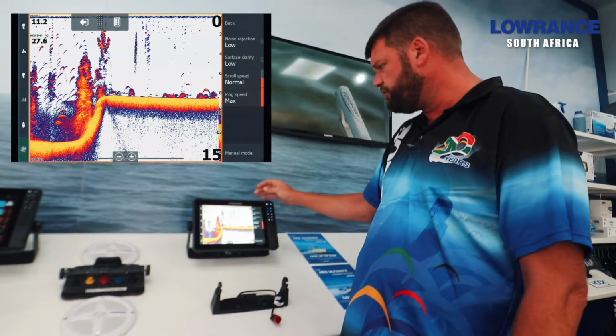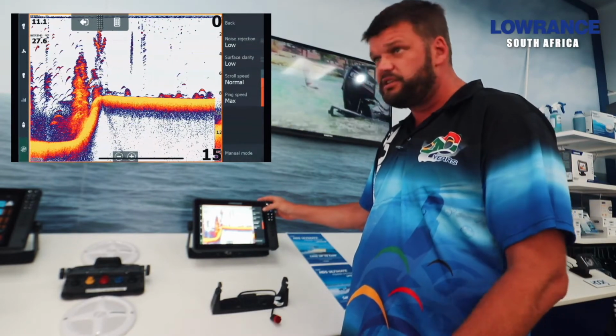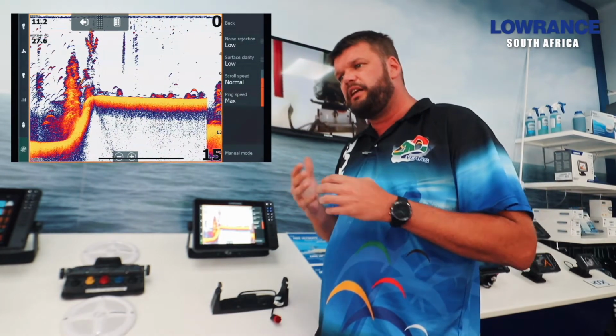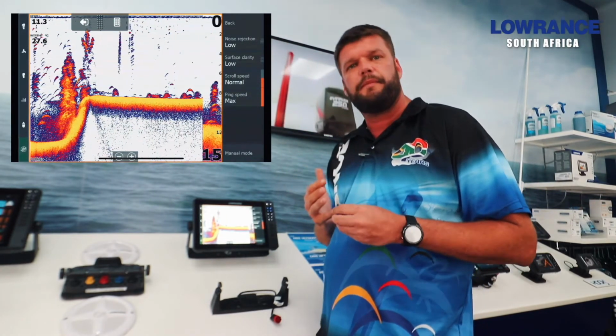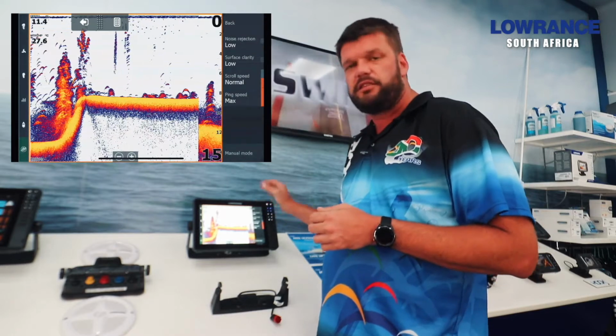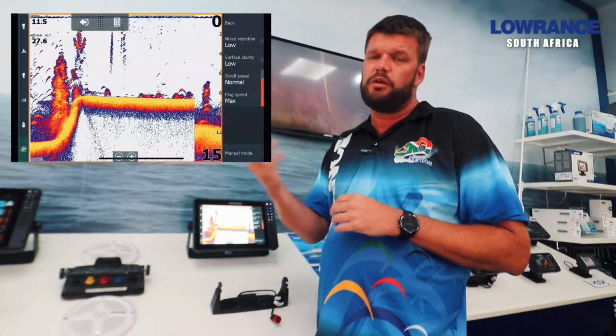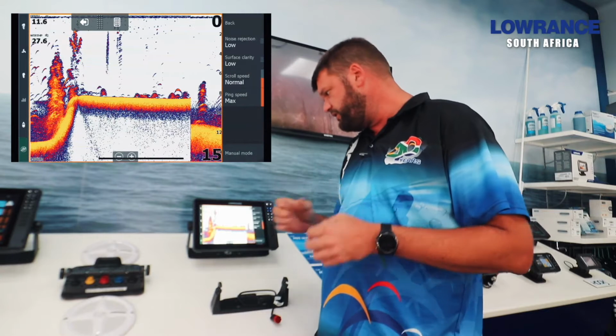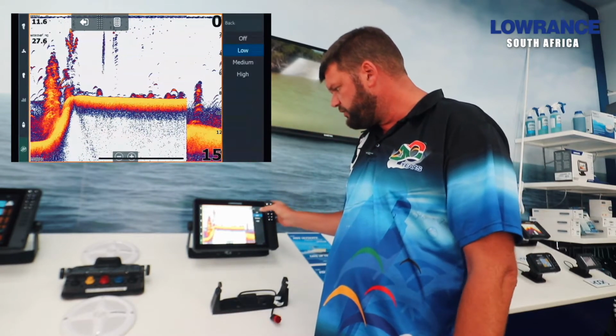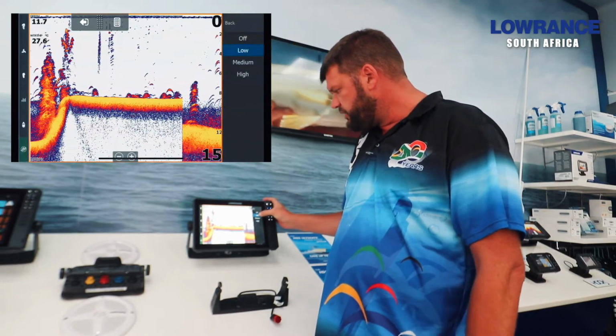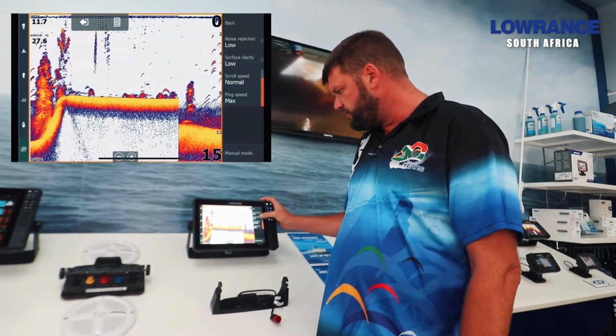On the advanced settings, noise rejection is low. If you've got cables running past any electrical interference, this is where we adjust it. If your transducer cable is running with your wiring loom and you're getting a bit of interference, this is where we play with it. We've got low, medium and high, and generally I leave it on low if there's not too much interference.